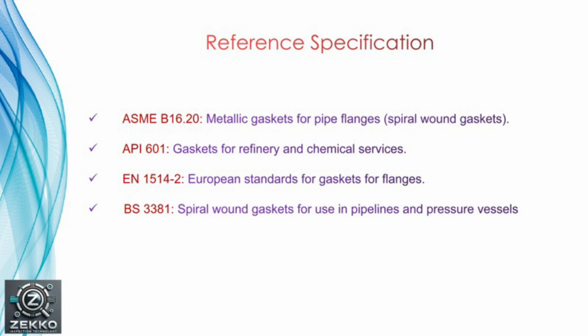Another specification is API 601, which is used for metallic gaskets for raised face pipe flanges and flange connections. The scope is the same, design, dimensions and tolerances are covered in this spec. Now another spec mentioned here is EN 1514 Part 2. This is a European standard for gaskets for flanges. Another is the British standard BS 3381, spiral wound gaskets for use in pipelines and pressure vessels.